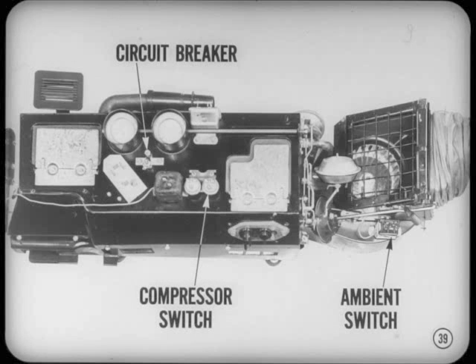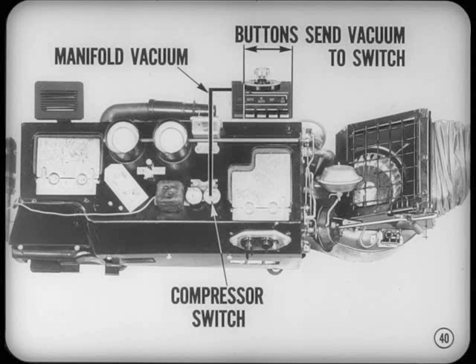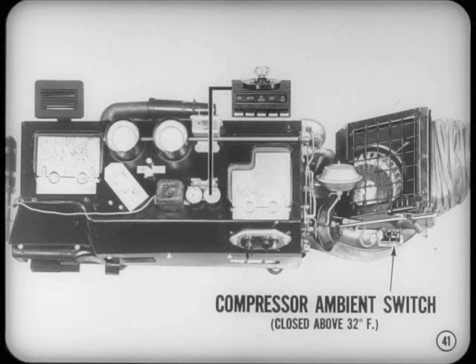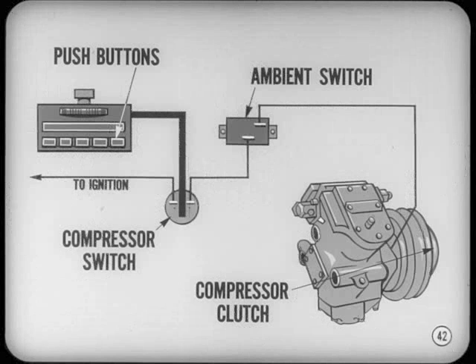The electrical circuit includes a circuit breaker, or a fuse, a vacuum-operated compressor switch, a compressor ambient switch, and the compressor clutch. Pushing any button except the off button sends vacuum to the compressor switch. This closes the switch contacts. That's because the compressor switch is vacuum operated by a manifold vacuum connection controlled by the push button switch. It isn't connected into the control vacuum circuit in any way. Next in the clutch circuit is the compressor ambient switch. It is a temperature-sensitive electric switch, and it stays closed as long as ambient or incoming air temperature is above 32 degrees. At lower temperatures, the switch contacts open. From this clutch control circuit diagram, you can see that the clutch circuit is controlled by the push buttons and is independent of the automatic control circuits.